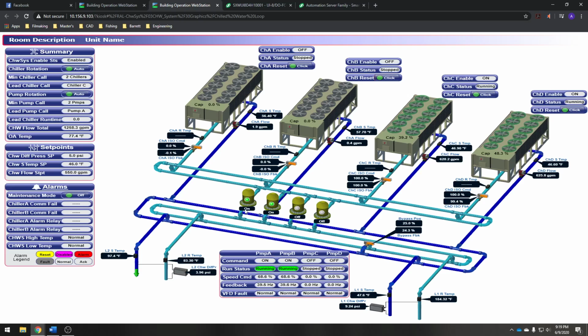We modulate the pump speed based off a differential pressure, a pressure reading difference between the supply and the return lines. That number is just a number we picked. We kind of just know what the system should run at. It's an engineered solution. So 5 psi is just a good starting number for this particular system. These pumps are controlled by this differential pressure reading, so they will spin up and down, modulating to maintain this differential pressure.